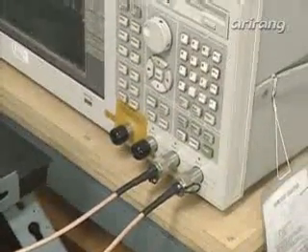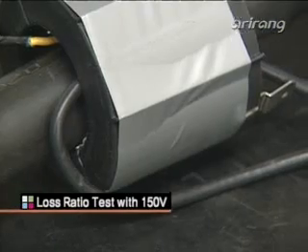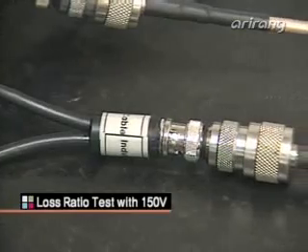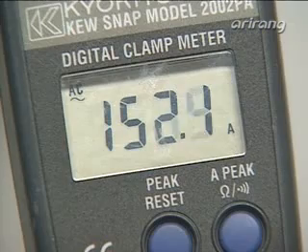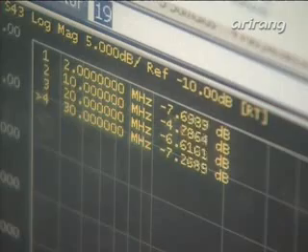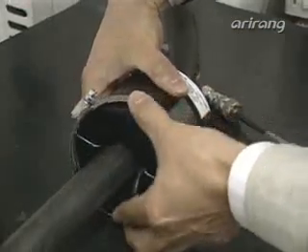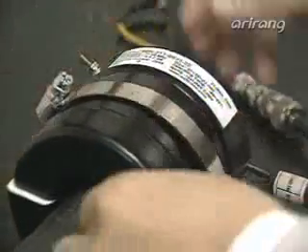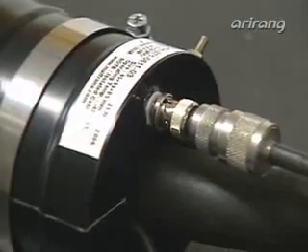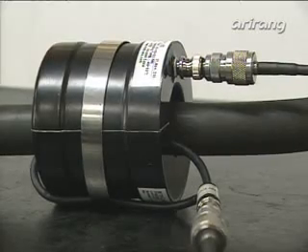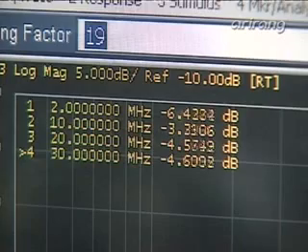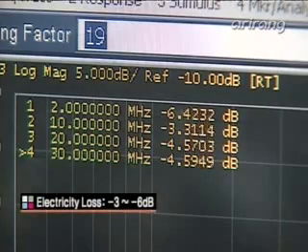Applying 150 volts to both the existing inductive coupler and the Matron coupler to measure electricity loss, the existing inductive coupler lost electricity by minus 4 to minus 7 dB, while the Matron coupler lost only minus 3 to minus 6 dB. Although these numbers may not seem very different, there is a huge difference between the two in terms of power line communication. Even signals outside the frequency band for power line communication are coupled in the existing couplers, but Matron developed a technology to remove those noisy out-of-band signals.